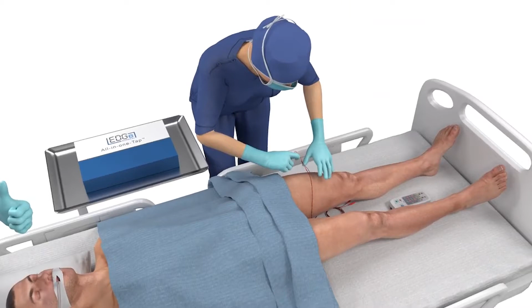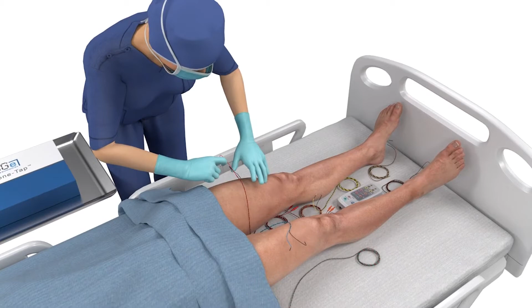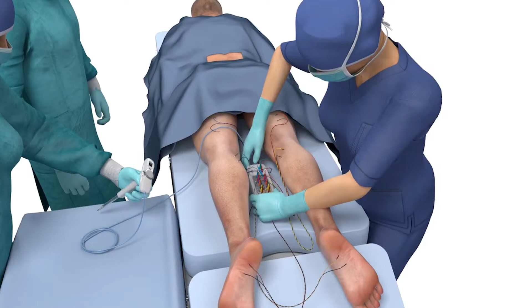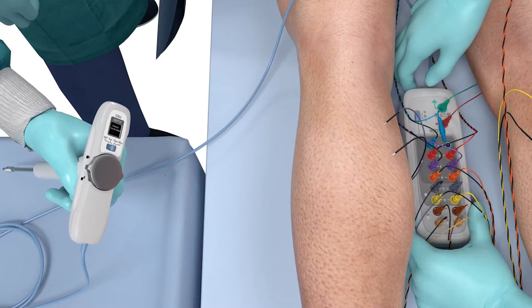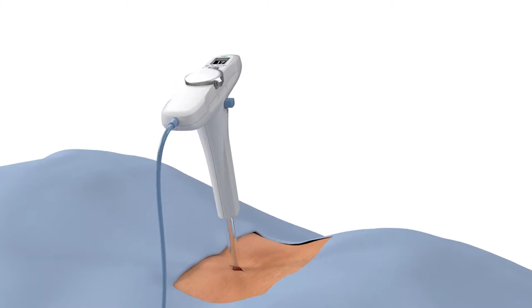Once the patient is anesthetized, an HCP places the muscle electrodes in the appropriate muscle groups correlating to the nerves being operated around. Next, the patient is positioned on the operating table, and the electrodes and all-in-one tap are all connected to the smart junction box and turned on. If any of the electrodes are not connected correctly, the all-in-one tap and smart junction box will indicate an error with a flashing red light and a check electrode display on the handpiece screen instructing the HCP which loose electrode needs to be corrected. The tip of the device is placed at the entry point of the pedicle and can be malleted for advancement.